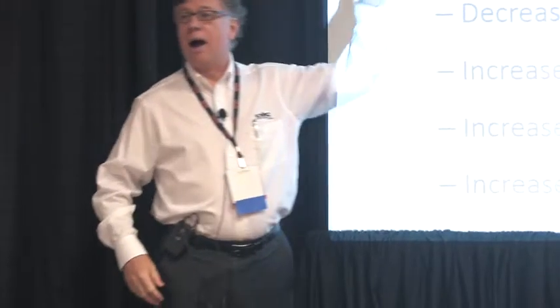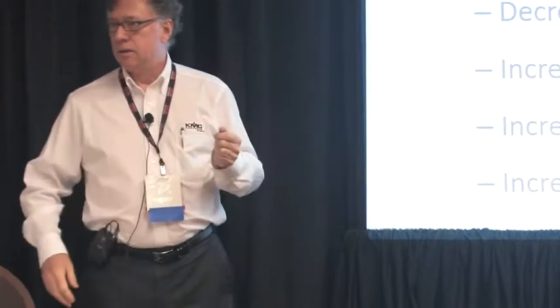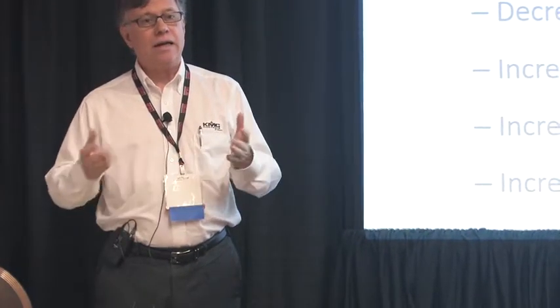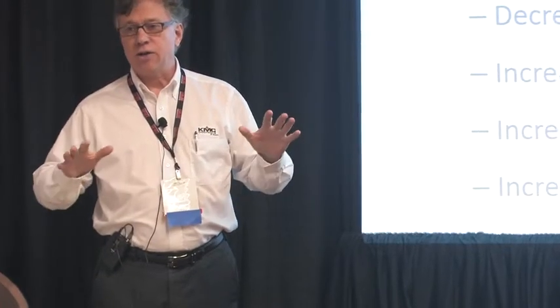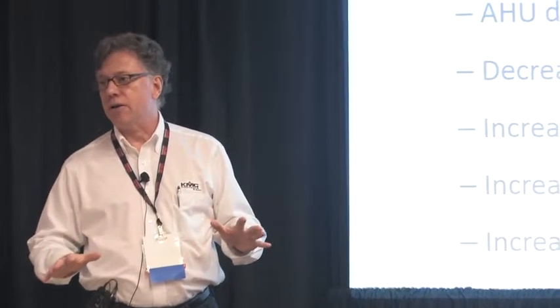You can do things like, if it's a VAV job, a project with VAV boxes and an air handler, you can bring information back from the VAV zones about how much air they need. If they don't need as much air, you can actually lower the duct pressure on the air handling units. And when you lower the duct pressure, it's an exponential curve as far as the amount of energy you're going to save from the fan energy.